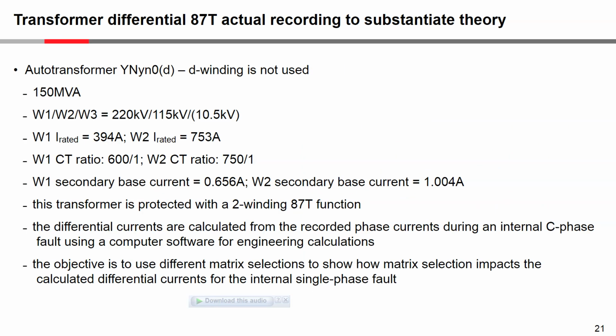So here's an actual example. This transformer exists. And what happened is, I won't go through the details of the whole transformer. It was an auto transformer. The D-winding is not used. So it had a two-winding differential, looking at winding 1 and winding 2.